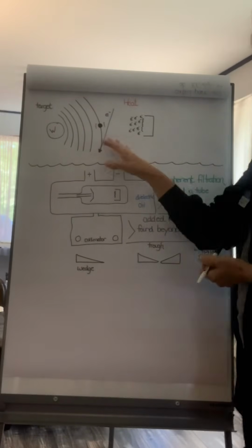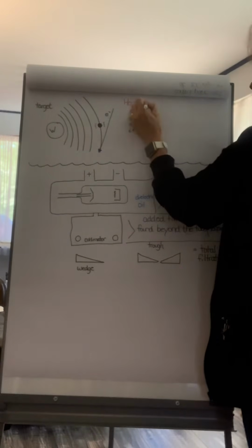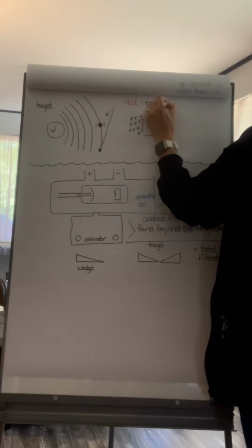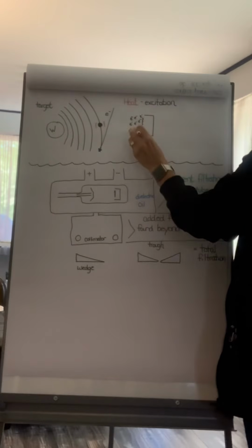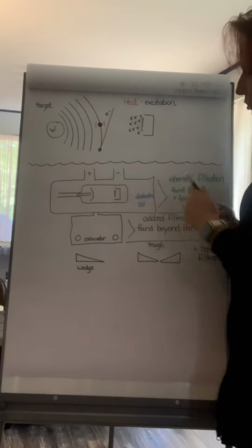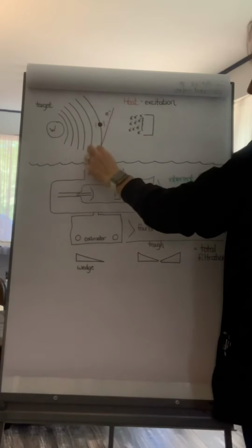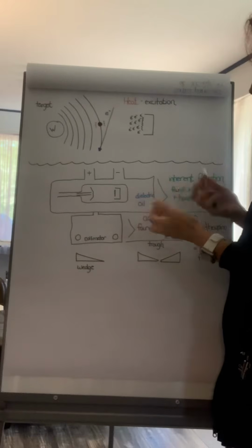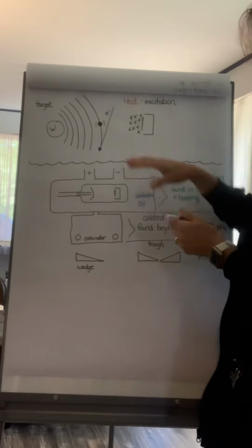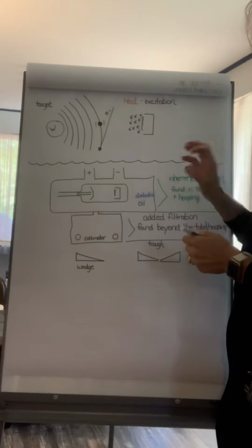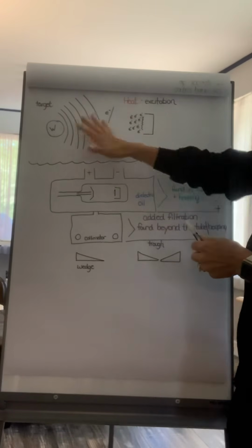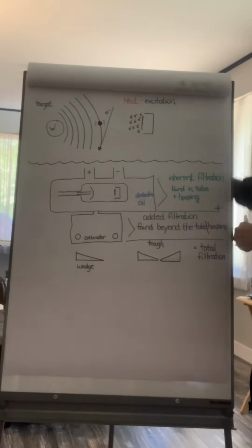So this is actually called an excitation, because what happens is that excitation, that electron, the filament electron, or the incident electron, or the projectile electron passes by, raises this outer shell electron to a higher energy state. It has to get rid of that excess energy, and it does so in the form of infrared radiation or heat. And this is what happens the bulk of the time. Okay, so that's our first and most prominent interaction.